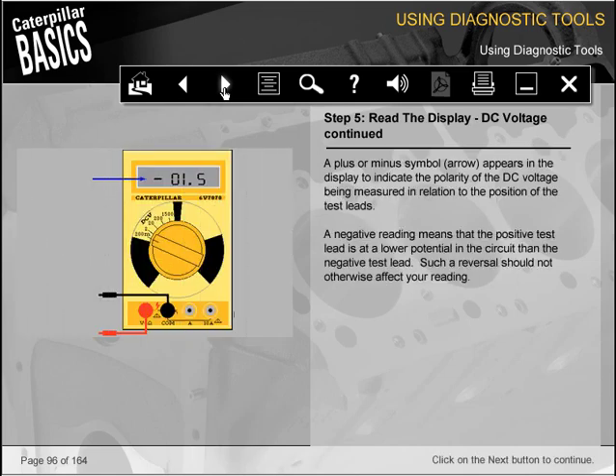A plus or minus symbol appears in the display to indicate the polarity of the DC voltage being measured in relation to the position of the test leads. A negative reading means that the positive test lead is at a lower potential in the circuit than the negative test lead. Such a reversal should not otherwise affect your reading.